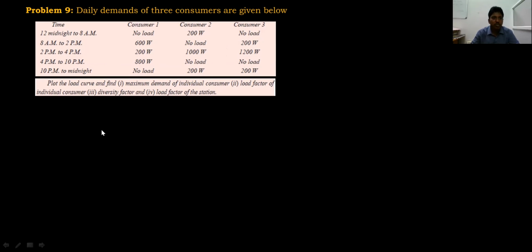The second question is the load factor of individual consumers. Load factor is equal to the number of units consumed divided by maximum demand into time. Time is 8760 hours for a year; if it is given for one day, it is equal to 24 hours. And the maximum demand of consumer 1 is 800.